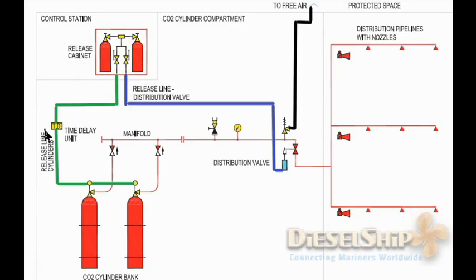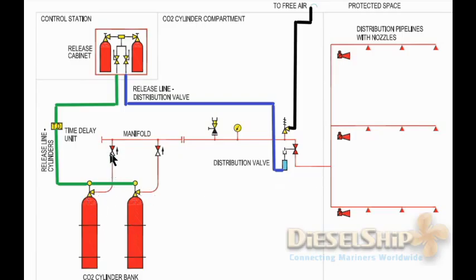Electronically, we have a solenoid valve and a timer mechanism which, after 20 seconds time delay, opens the solenoid so the CO2 goes and opens the main cylinder unit. As the chief engineer opens the main distribution valve, a limit switch gives an indication that the valve is opened. After the time delay, the main CO2 bottles for the engine room are also opened. CO2 passes through the non-return valve — each cylinder outlet has a non-return valve — reaches the main manifold, and through the distribution valve goes to the engine room, distributed to various nozzles on various platforms.